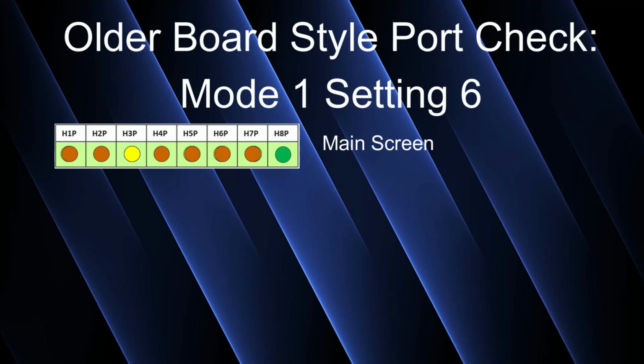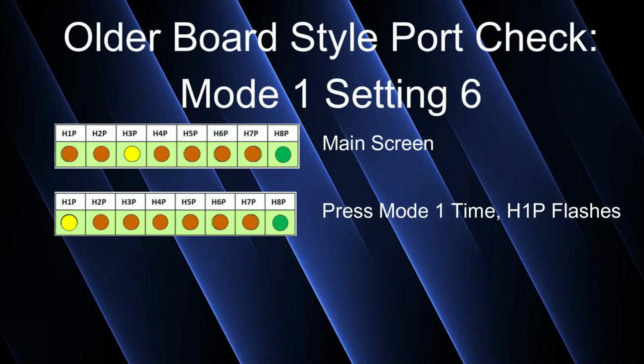So from the main screen, always start from the main screen. Again, we're going to start from the old board. H3P is solid. You're going to press the mode button one time. This time you're going to go to monitor mode 1, setting 6. So with H1P flashing, telling you are in monitor mode 1, you're going to press set 6 times.